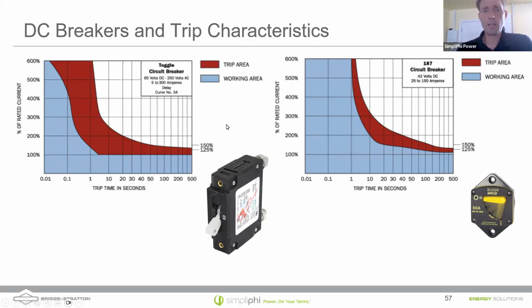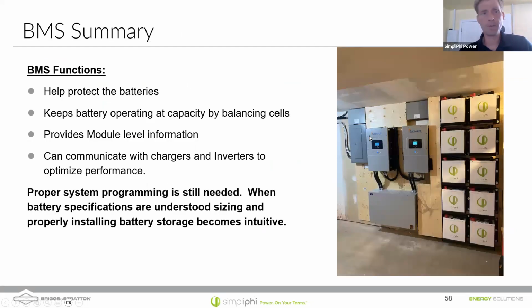Breakers, it's just important to note here, the point of this slide is to tell you that the breakers don't often trip rapidly. They trip slowly, and some of these breakers, you have to pay attention to the trip curves. And some of these breakers, you have to go above their rating in order to get them to trip at all. The higher you go above the rating, if I'm looking at 200% for the breaker on the left, it will trip in about 0.2 of a second, right? There's a log scale on the left. The breaker on the right, if I go at 200%, it would take 10 seconds for that breaker to trip. So if you're using breakers to try to protect your equipment, pay attention to the trip curves for those breakers.